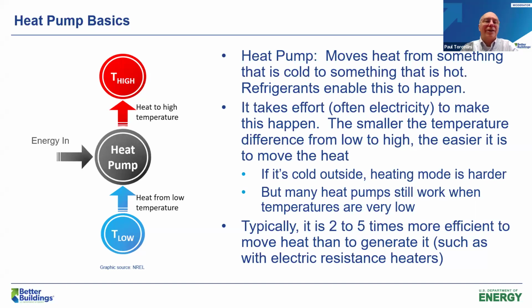You can think of it like climbing up a hill, from the bottom to the top, the effort takes effort, and so that effort is often electricity. The smaller the temperature difference from low to high, the easier it is to move that heat. So the colder it gets outside, the harder it is to push that heat to a warm location. But many heat pumps today will still work when temperatures are very low. One of the advantages of a heat pump is that it is typically 2 to 5 times more efficient to move the heat than it is to generate it, such as using electric resistance heaters.